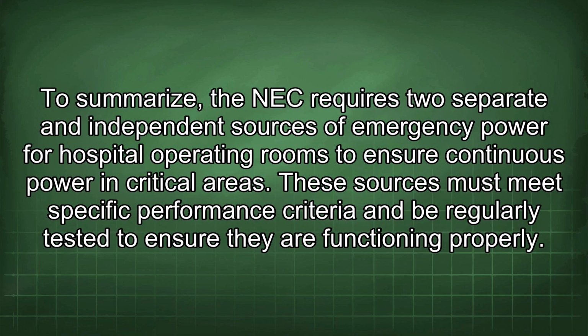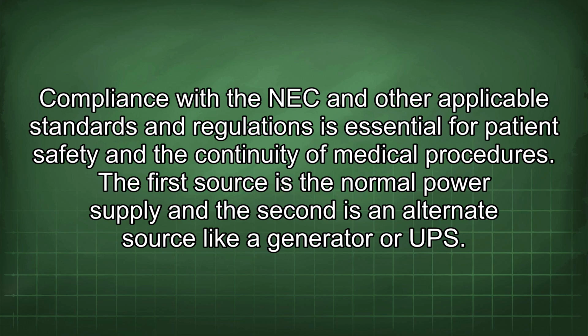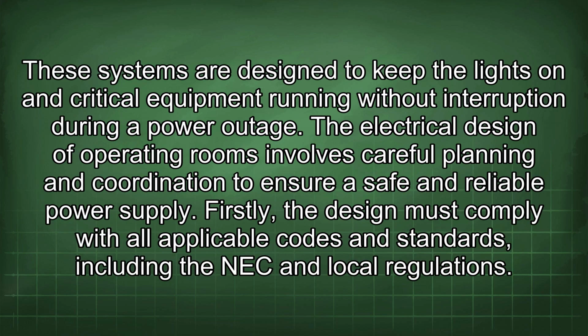To summarize, the NEC requires two separate and independent sources of emergency power for hospital operating rooms to ensure continuous power in critical areas. These sources must meet specific performance criteria and be regularly tested to ensure they are functioning properly. Compliance with the NEC and other applicable standards and regulations is essential for patient safety and the continuity of medical procedures. The first source is the normal power supply, and the second is an alternate source like a generator or a UPS.